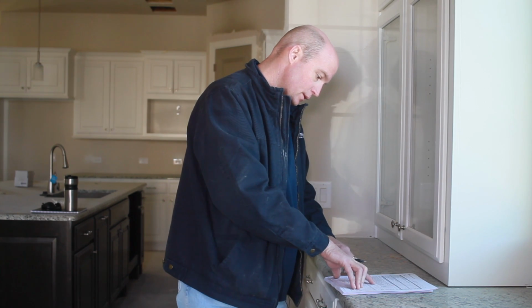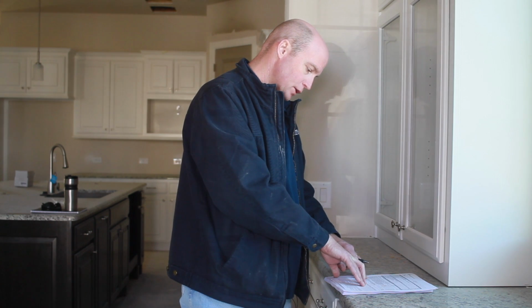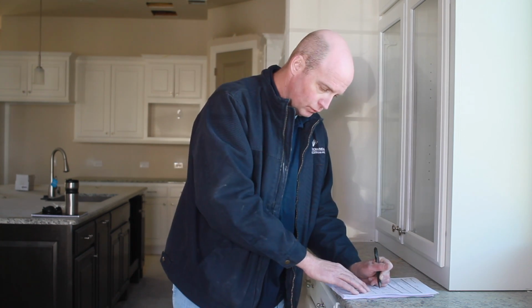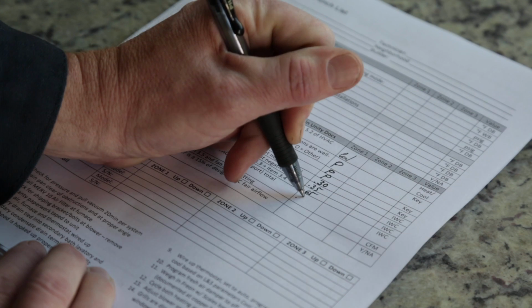Measured total external static pressure on the design report. Simply put, that you'll get that off your iPad. All of the superintendents will have access to that. What was the system designed to? When the design team designed it, what was their external static pressure designed up to? And we designed for anywhere from 0.75 to 0.8. So we'll put 0.75 there.